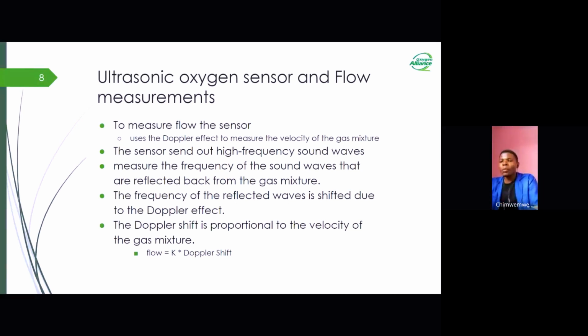To put it simply, an oversimplified equation is that flow rate is equal to K1 times the Doppler shift, which is caused by the Doppler effect I've just mentioned. This K1 is a calibration constant, and it is set by the manufacturer. As I have already said, the constant is determined by the manufacturer of the ultrasonic oxygen sensor. It is typically determined by calibrating the sensor against a known flow rate. So this is all done at the manufacturer's end.